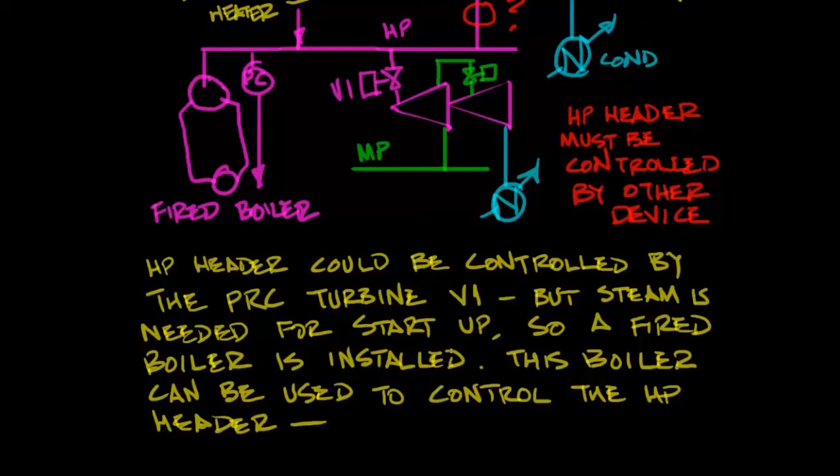In this case we show a fired boiler connected to the HP header that will provide that startup steam and then once you're running and making product you don't need that much steam from the fired heater but it can be used as a compensation for any swings in that HP header pressure. Since the CGC turbine is not controlling its extraction header and you've got a bunch of other users on that header pulling steam out of it you need something to supplement the steam if they're not in balance and that's what you would get from the fired heater.